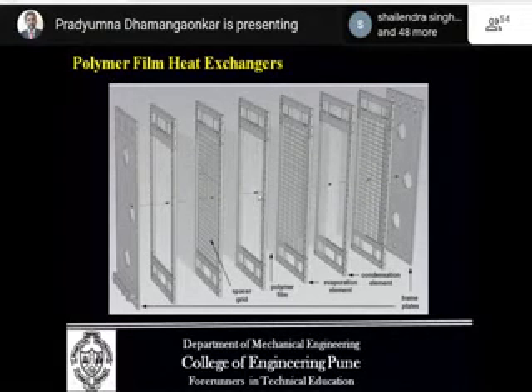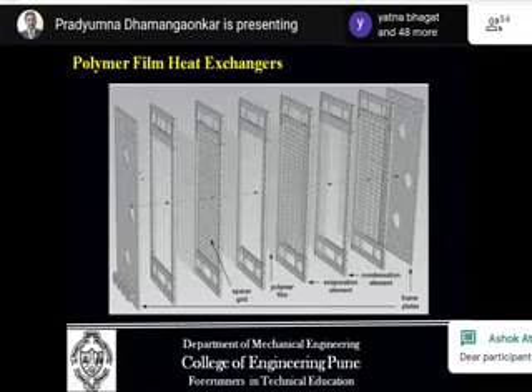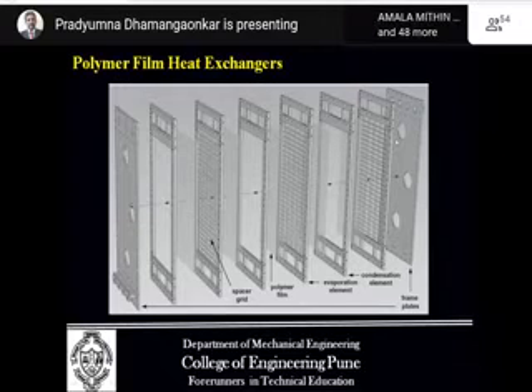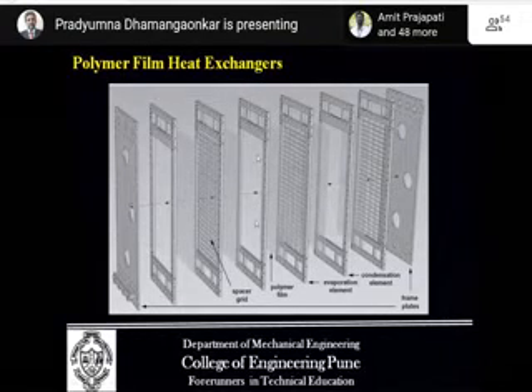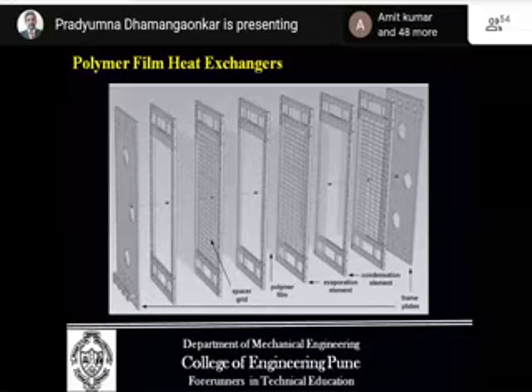And these polymer films are very thin, very light duty films, just similar to the plate type heat exchanger. They can be stacked and they will also perform the same type of operation. The only problem with this polymer film is the lower thermal conductivity. In case of metal, as the thermal conductivity is higher, the heat transfer from hot fluid to cold fluid is higher. But if this film is made up of a polymer having a lower thermal conductivity, of course it will offer higher resistance to heat flow.